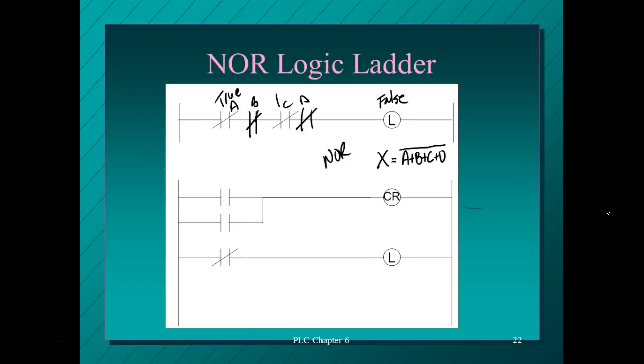Right? And what you do is you remember it says NORs and NANDs are what's required to turn the load off or make the rung false. ANDs and ORs are what's required to make the rung true. Right? You understand? Yes or no? Yeah. So if I put a bunch of contacts in normally closed contacts, the only thing I can get is to open up all those contacts to get the rung to go false, right?